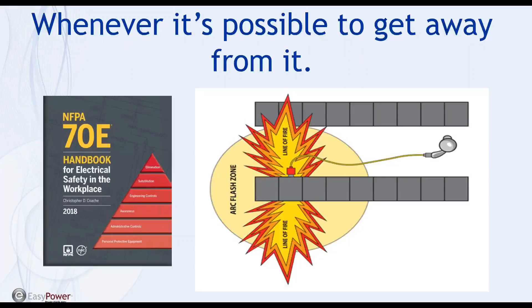And finally, it's a great solution whenever it's possible to get away from it. Looking at that hierarchy of hazard control measures, even if the incident energy isn't at 40 calories, maybe it's 20 - there are still situations close enough that I wouldn't want to be standing in front of it. And if the solutions are available to get away, or if I don't have things like current limiting devices or protective relays in place, it makes sense to utilize remote switching or racking.